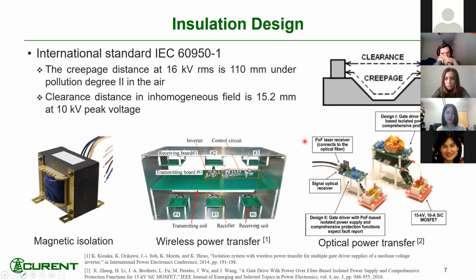For the insulation design, there are two parameters that gauge this insulation capability. One is the creepage distance, the distance along the surface between two objects, and another is the clearance distance, the distance in the air. For different insulation voltages, there are different creepage distance and clearance distance requirements. This requirement is also affected by the purity of the air. If there are dusts and water drops in the air, it would need more clearance distance.